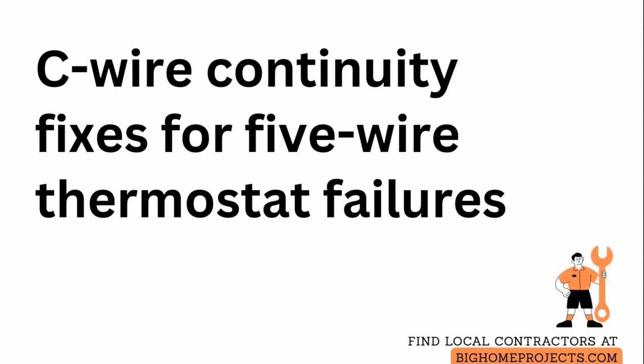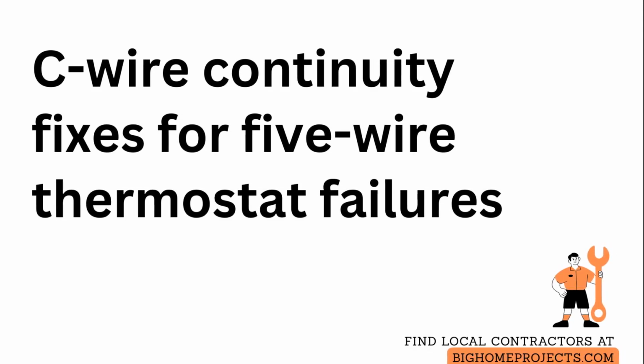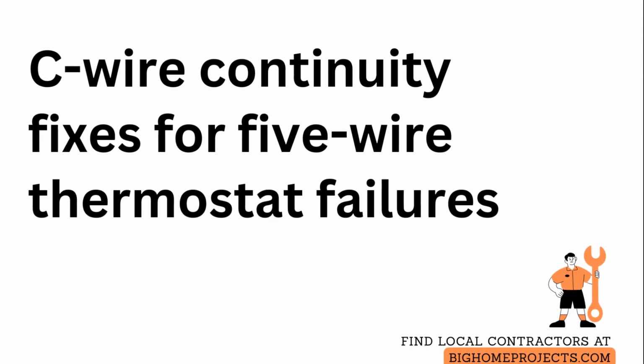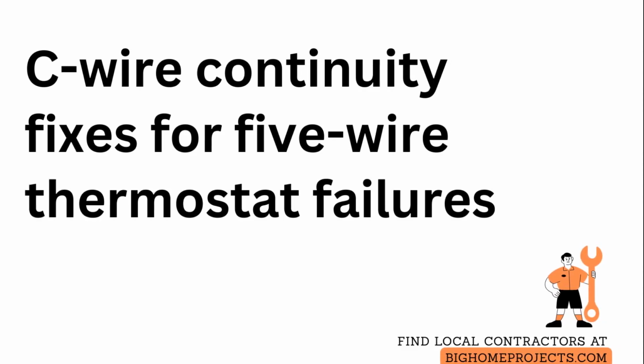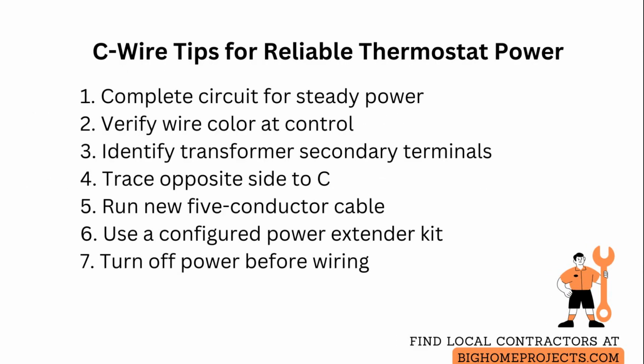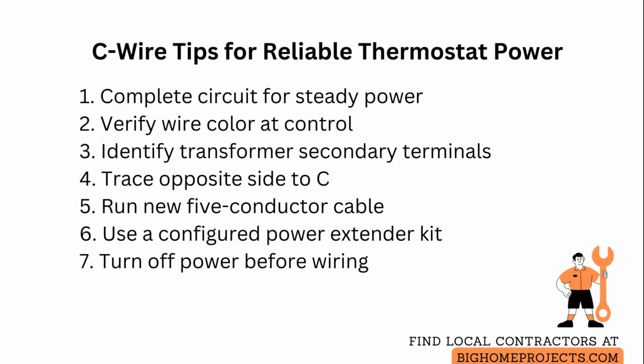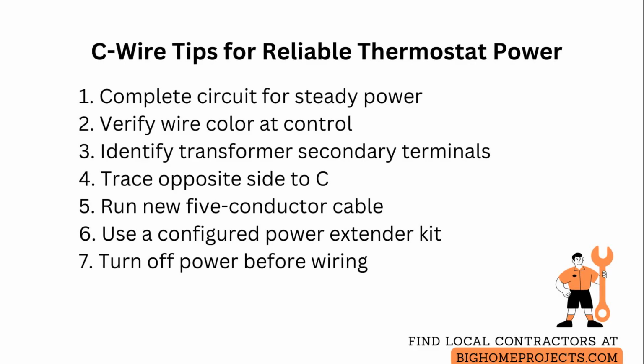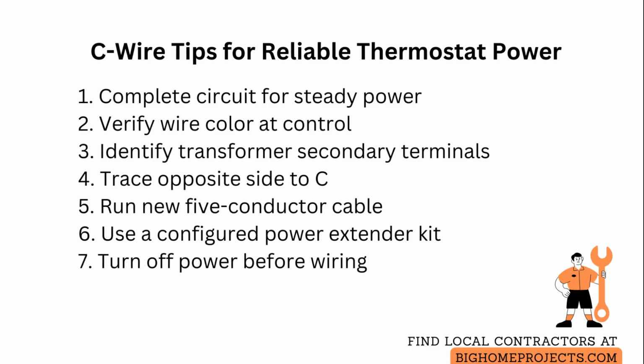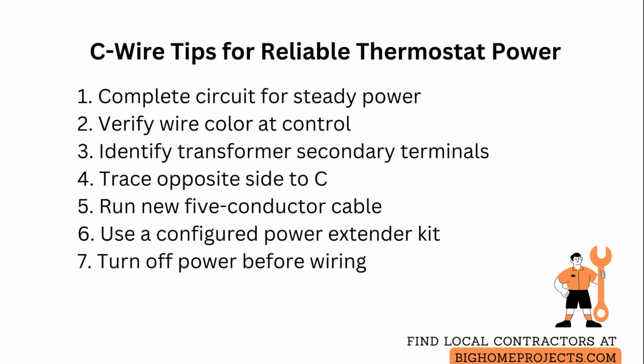The common wire completes the 24-volt circuit to provide continuous power to a thermostat, so it does not rely on batteries. A common wire, often called the C-wire, is the return path for the 24-volt transformer that powers modern smart thermostats and controls. It completes the circuit from the transformer secondary and feeds the thermostat with steady power rather than intermittent battery power, which prevents frequent battery changes and rebooting.